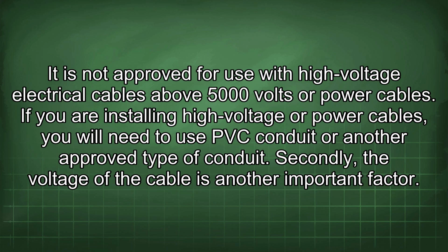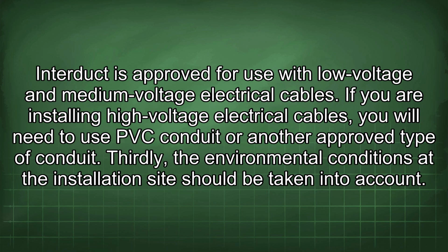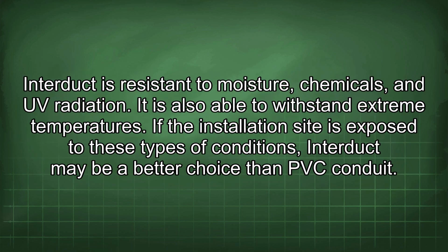of conduit. Secondly, the voltage of the cable is another important factor. Interduct is approved for use with low voltage and medium voltage electrical cables. If you are installing high voltage electrical cables, you will need to use PVC conduit or another approved type of conduit. Thirdly, the environmental conditions at the installation site should be taken into account. Interduct is resistant to moisture, chemicals, and UV radiation. It is also able to withstand extreme temperatures. If the installation site is exposed to these types of conditions, Interduct may be a better choice than PVC conduit.